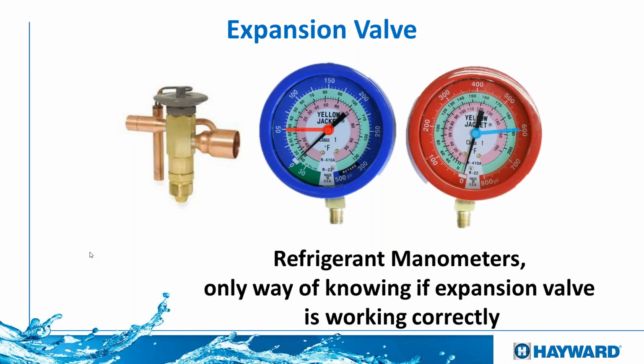And what happens, for people that know how gauges work, is that when the heat pump is off, it's going to have a stabilized pressure. For example, the low pressure will be at 150 and the high pressure will be at 150. But when the heat pump comes on, the high pressure one will tend to go all the way up to the maximum, and at the same time, the low pressure will tend to go all the way to the minimum. So they will go to opposite sides. When we see this with manometers, we know that definitely the expansion valve is bad and needs to be replaced.